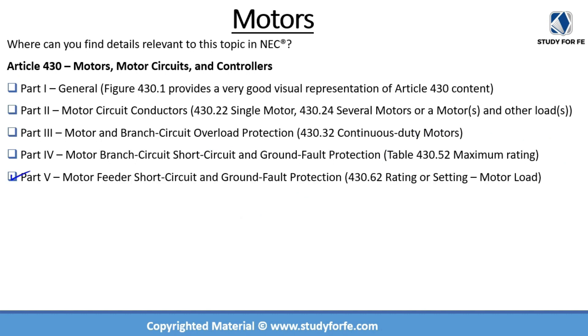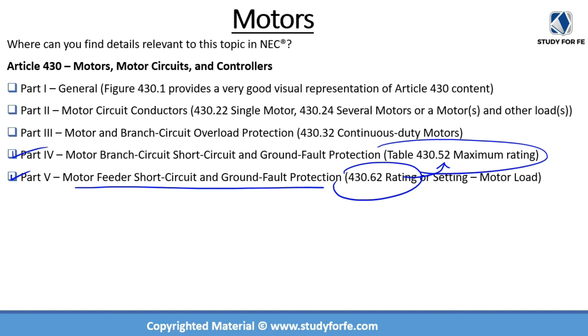Part 5 of Article 430 is titled Motor Feeder, Short Circuit and Ground Fault Protection. The section I would like you to go through in detail is 430.62, which covers the rating or setting of a motor load, and it cross-references 430.52. I am going to go through a couple of examples on Motor Branch Circuit, Short Circuit and Ground Fault Protection as well as Motor Feeder, Short Circuit and Ground Fault Protection, to explain how we size OCPDs for both feeder and branch circuits.